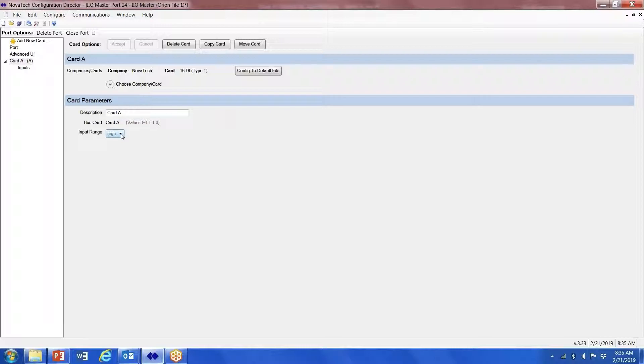Here we define whether we're using a high or low voltage input to apply the wetting voltage. Low would be 48 volts, high would be 125 volts. Once we've done that, now we could give Card A a specific name if we wanted to, but I think most people leave it as Card A.